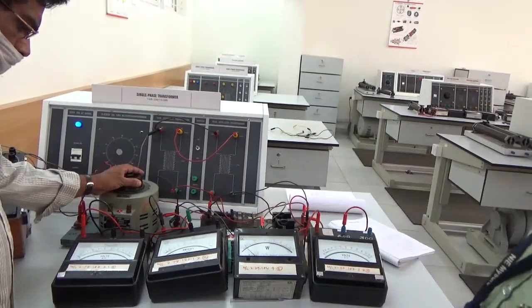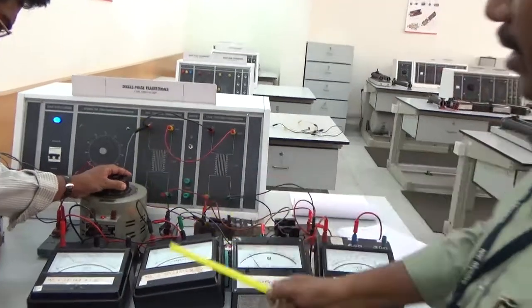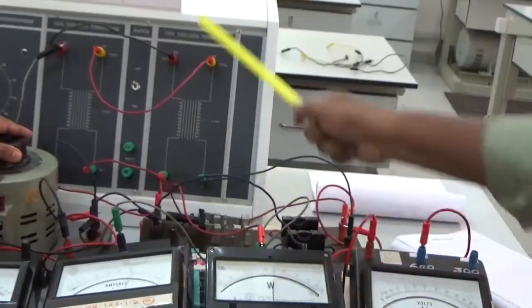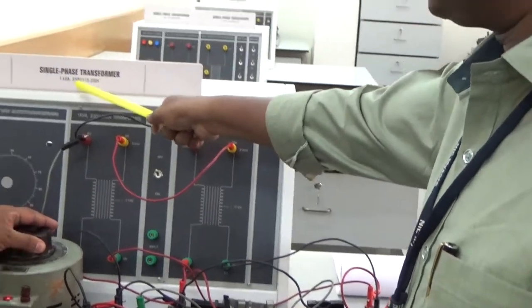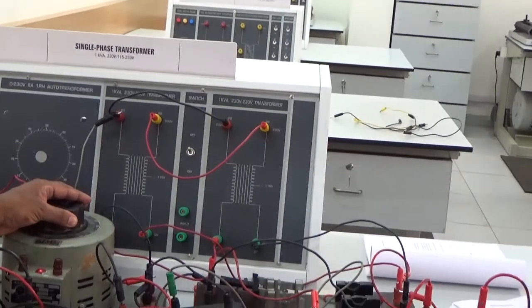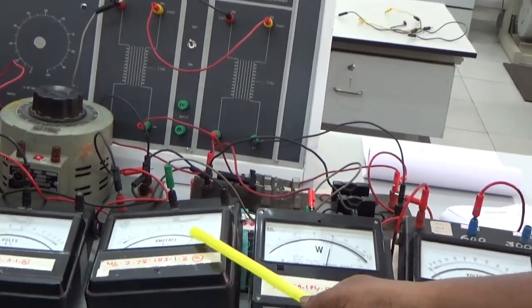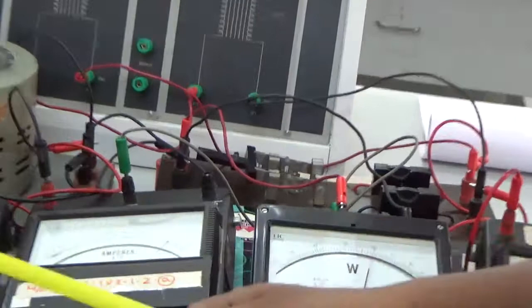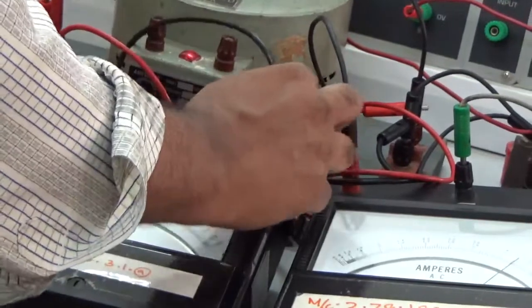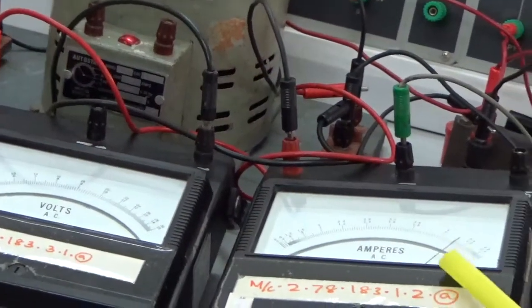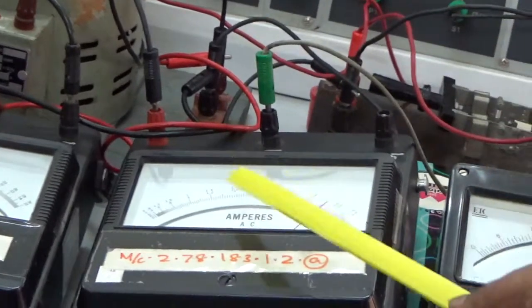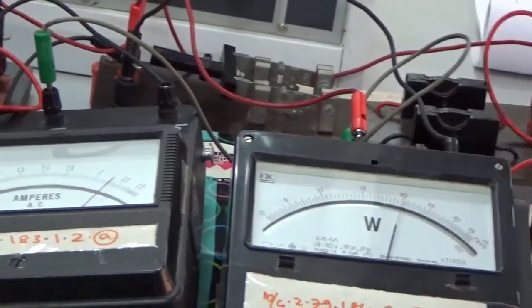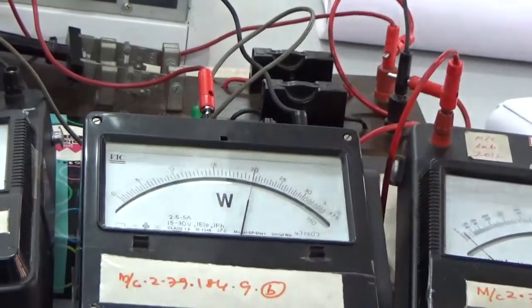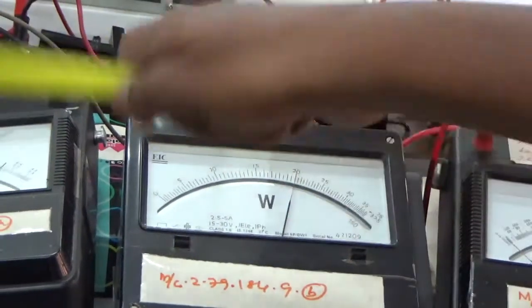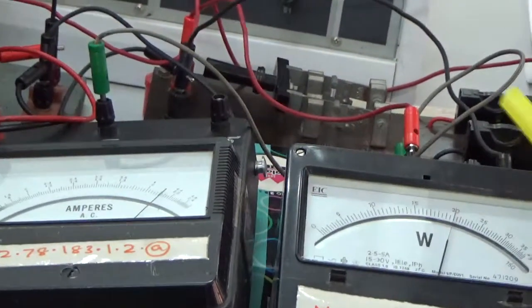I am injecting a small voltage, and it is increased until the rated current flows through the meters. Rated current is 1 kVA divided by 230, which is 4.6 amps. So you have to vary the voltage till 4.6 amps. This takes a small voltage, approximately 0 to 8 volts maximum. Because the secondaries are in series and shorted, the same current flows through the two transformers. So this is nothing but a short circuit test, and at that time you note down the wattmeter reading.